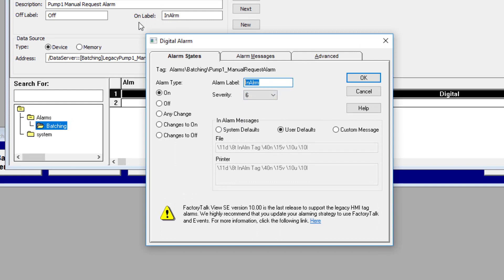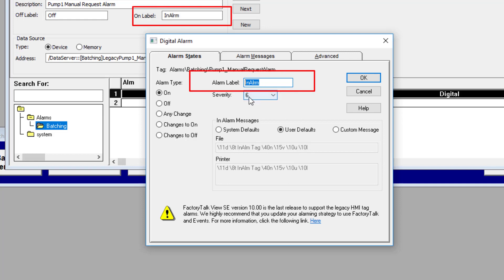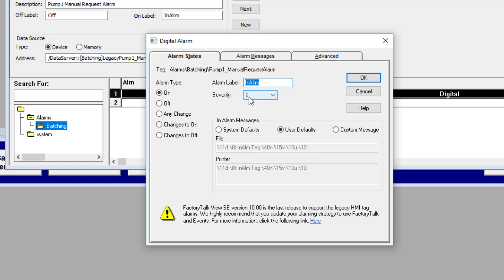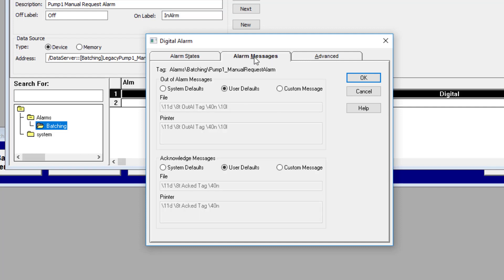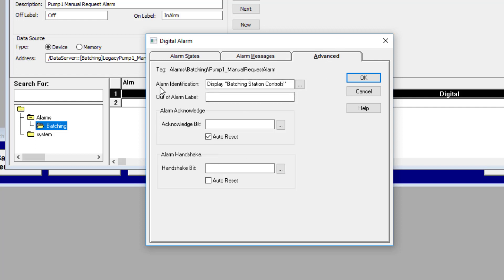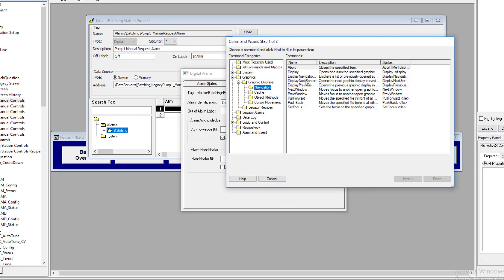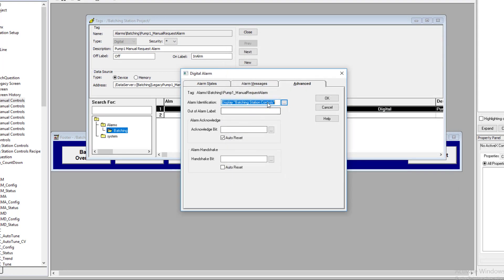This right here is your label — that's what you want to display on the screen when the alarm is active. In the Advanced tab, you have an Alarm Identifier. The alarm identifier is very much like what's inside the ALMD instruction. You have the ability to pull up a screen — you can go to Navigation, pull up a screen, and navigate to it. I'm currently pulling up the Batching screen.